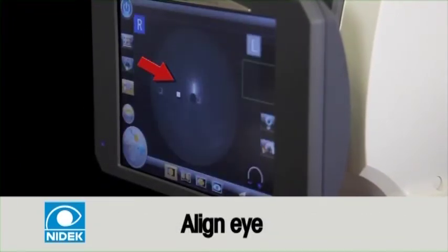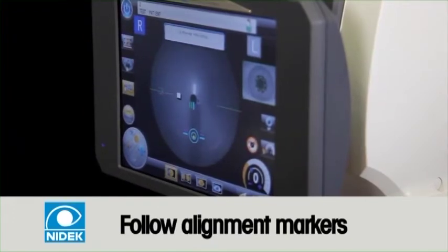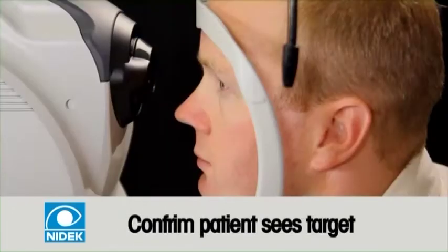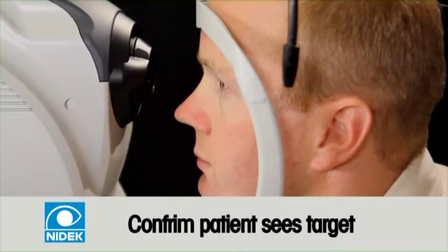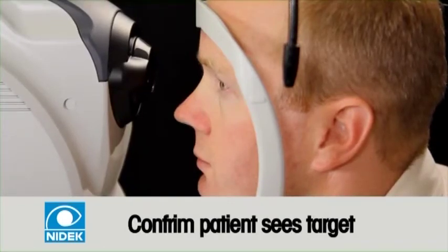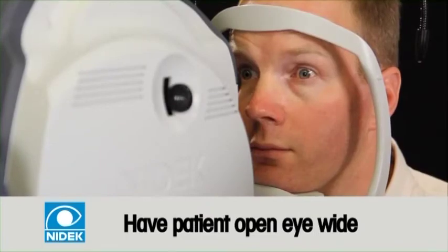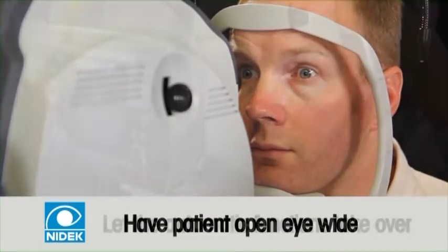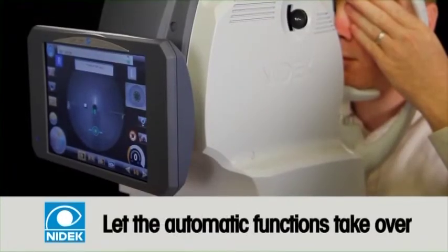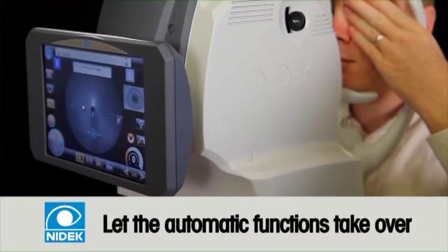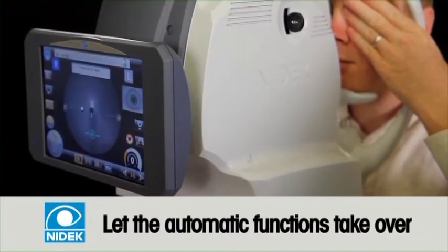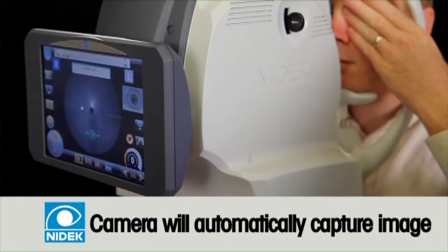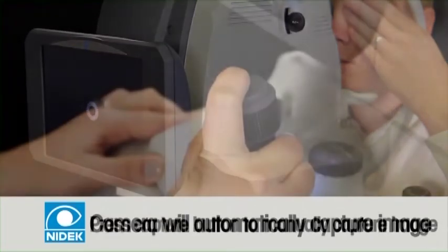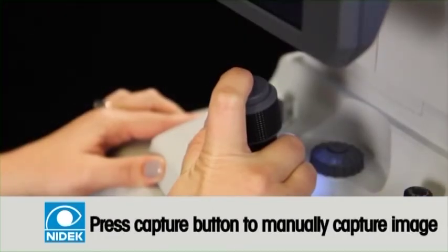At this point, your alignment markers will appear. Again, green meaning get closer and purple meaning pull back. Confirm the patient sees the target and instruct them to open wide and try not to move or blink. Have patient lift their brows to open wider if needed. Let the camera's automatic features take over. Their observation view will switch from the outside to the inside of the eye.